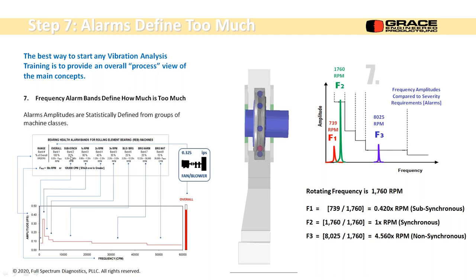We'll have subsynchronous, which is 20% of the overall level. That's the amplitude we're going to have. We have a 1 times RPM range, where it'll be 90% of the overall level. We'll have a 2 times RPM range, or twice running speed, at 40%, and 3 times is 30%, and blade pass frequency ranges and bearing defect ranges are 20, 25, and 15%. So we set this up with an idea of how machinery fails. If it's 1 times RPM, turning speed of the shaft, or some small harmonics of that, they're going to be a threshold type alarm. When we get out here, the way bearings fail, the alarm amplitude is very small. So we're trying to pick out really tiny peaks out of the spectrum and apply alarms to them.